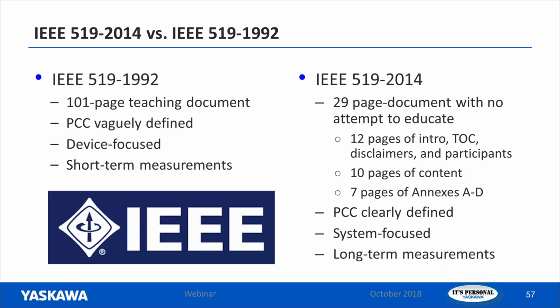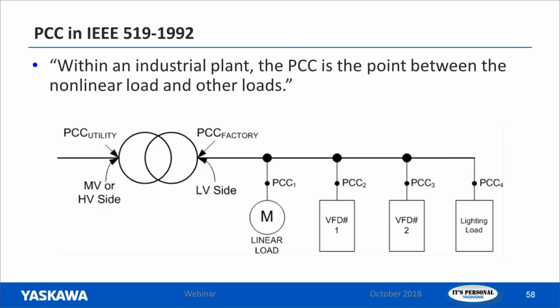The main thing gained here, of course, was the point of common coupling was more clearly defined, and they put more stress and emphasis that this is a system-focused standard, not meant to be applied to individual components. Here's kind of a visual example of how the PCC was viewed using the 1992 standard. So you've got your secondary side here with the transformer feeding your facility, and we call that the PCC, point of common coupling. Well, as you can see, the way this is depicted electrically, these are all the same points. So we ended up having specifying engineers and consultants and whatnot defining the point of common coupling at the terminals of each of these items, especially at the terminals of VFDs, which really was not the purpose of the standard.